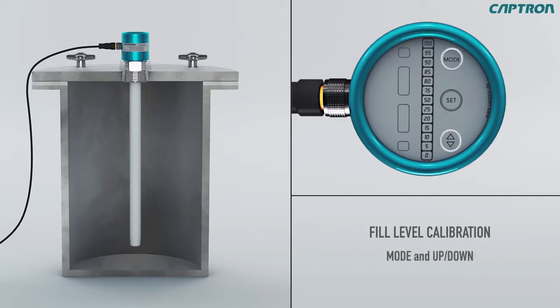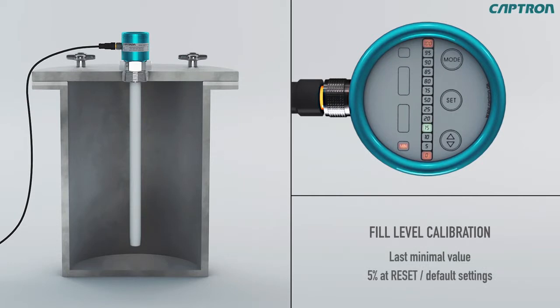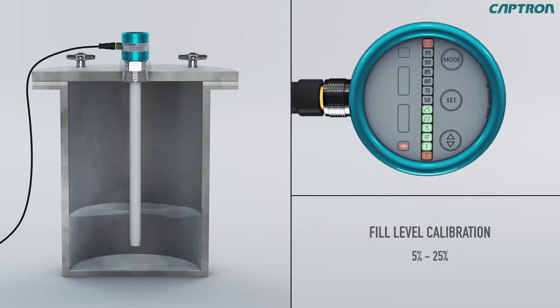Touch mode and up-down at the same time for approximately 5 seconds until the 0%, 100%, as well as MN light up. Now let go of all the buttons at the same time. The last set minimal value will blink. Now the probe will jump automatically to the minimum alignment. Fill the tank with 5 to 25% of the desired measurement range.